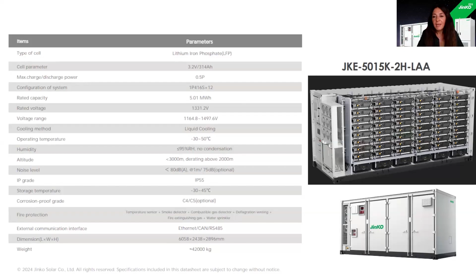This solution also has 12 racks. In the container, every 4 packs—the pack being that black drawer you see—connected in series make one rack. So there are 12 racks connected in parallel here, and they can be removed. We can also provide solutions where 12 racks mean 5 megawatt-hours, or go up to 6 racks, starting from a 2.5 megawatt-hour solution.